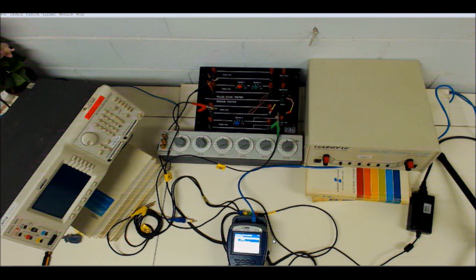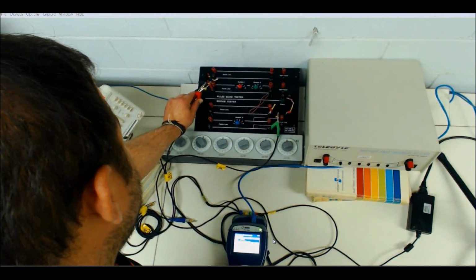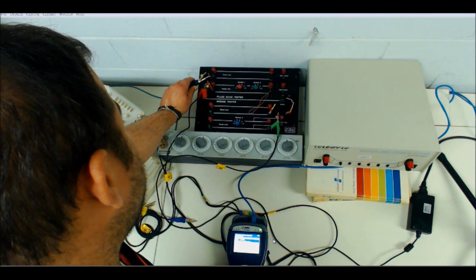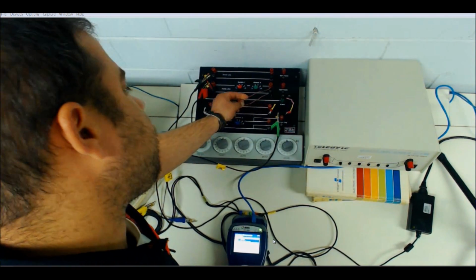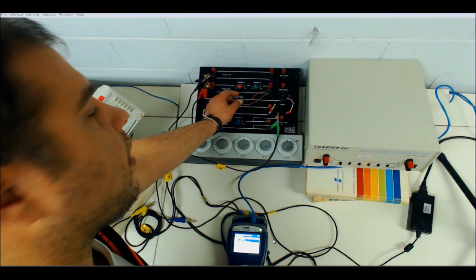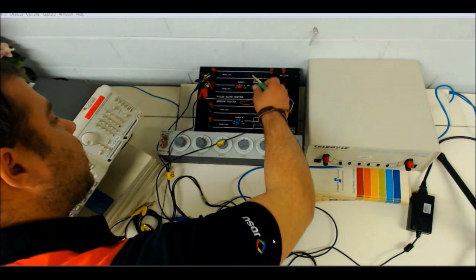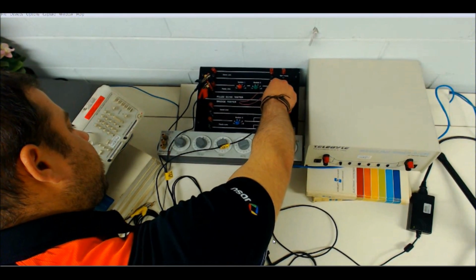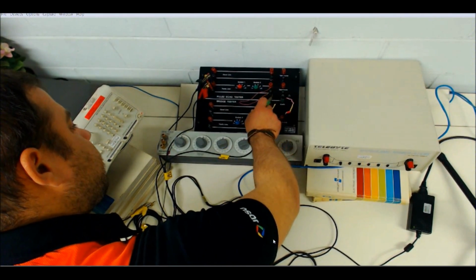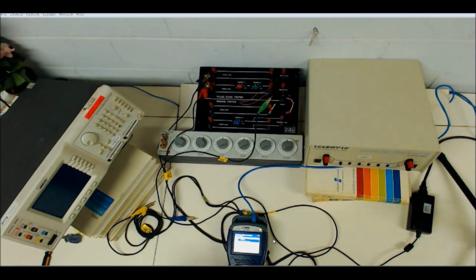In order to demonstrate this, I'm going to use this faulty line where I'm going to put my leads on, and I'm going to connect them. As you can see, I have short-circuited the end of the line just for the purpose of the demonstration. Now, I'm going to connect the earthing point of the unit to the end of the line, just to make the measurement more precise, and for you to see that the instrument is performing up to the specifications.